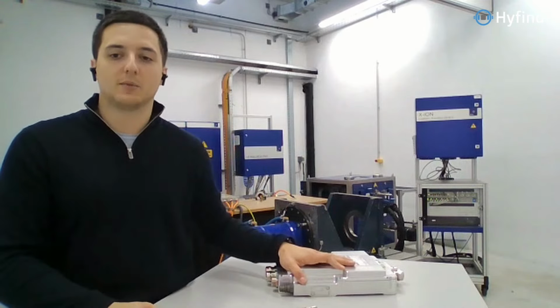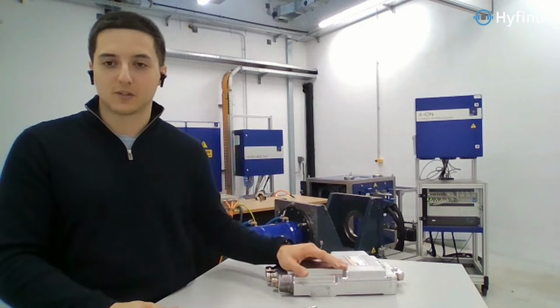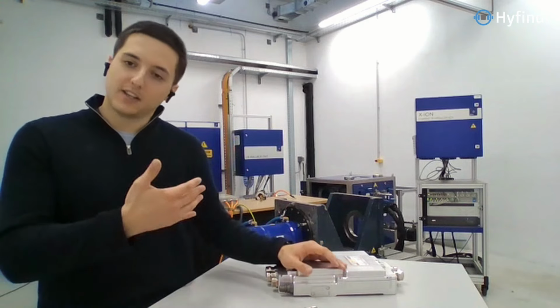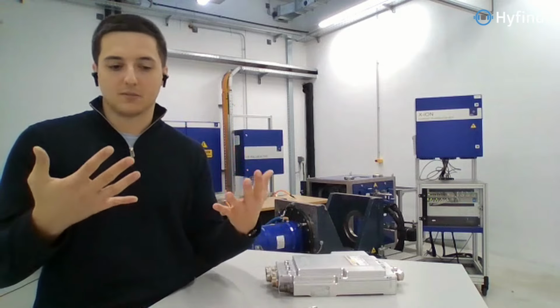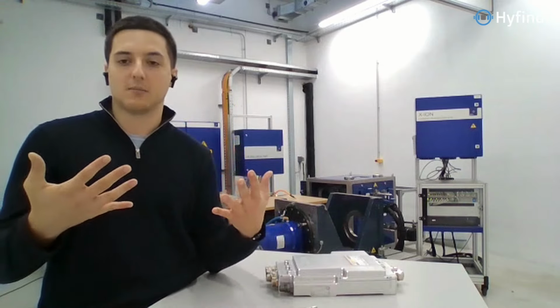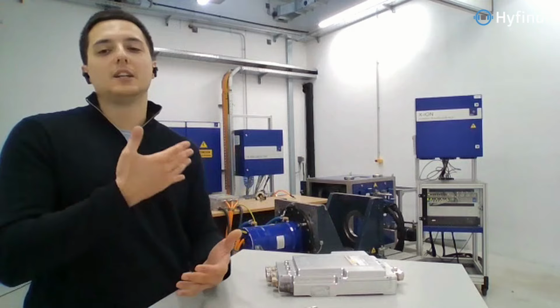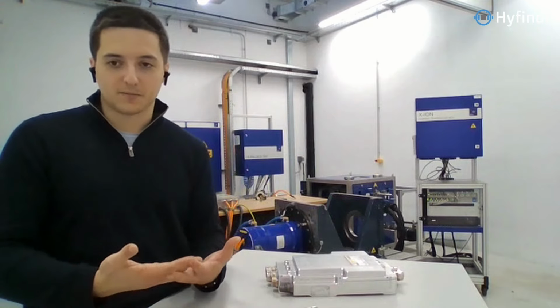Once we find a motor, we have to see that it matches our inverter specifications. If both components are physically matching together, then we need to pair them, so we need to calibrate the inverter for this specific motor.